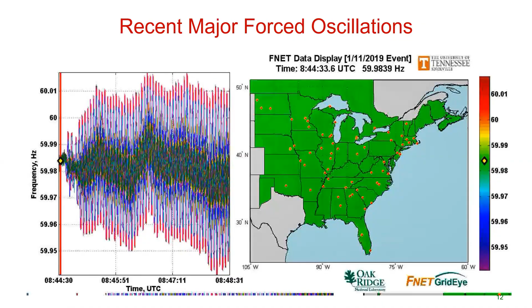But this one I'm showing you, another problem starting from Florida, is actually an oscillation that lasted 20 minutes. It's smaller in magnitude—if you look at the scale on the left, the frequency only changed a fraction of a hertz—but it's long-lasting, and it's possible for it to cause mechanical failures and other problems in the system. You don't want this either, and you need ways to suppress it as well.